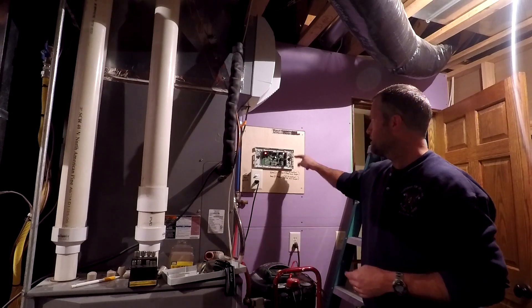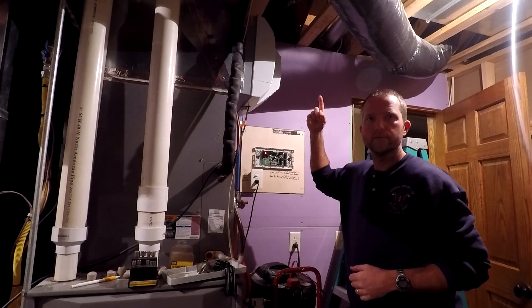I can actually test that voltage right here. And 26. That's a 24 volt system, anywhere between like 24 and 30 is good. I know that this board is probably working correctly, which is great because I don't want to replace this board. I'm hoping that it's something more simple up the line. The next thing I want to check is the other end of this wire which is up at the damper.